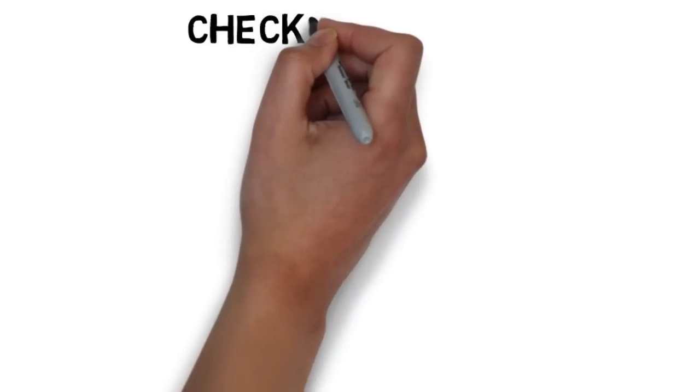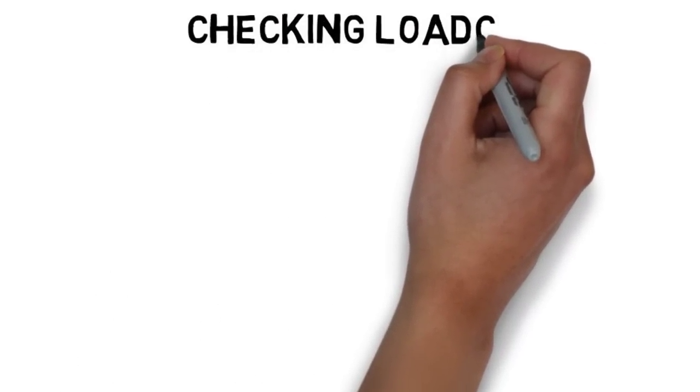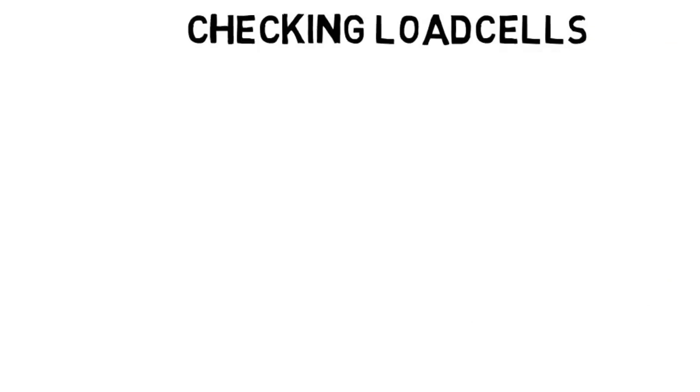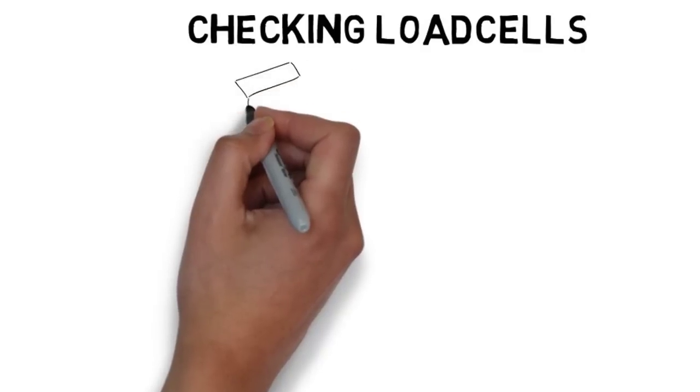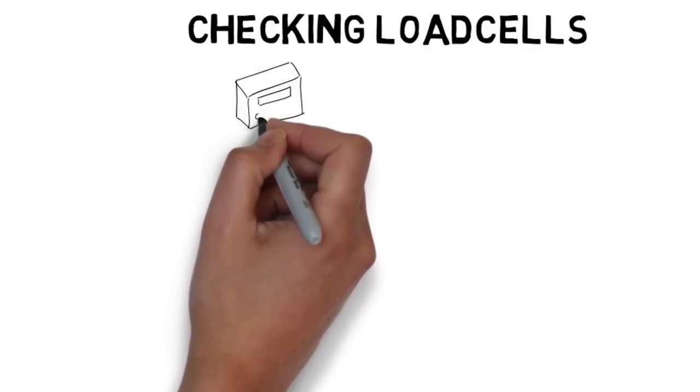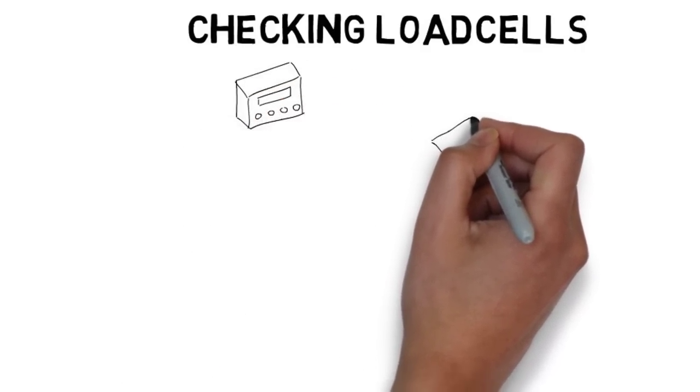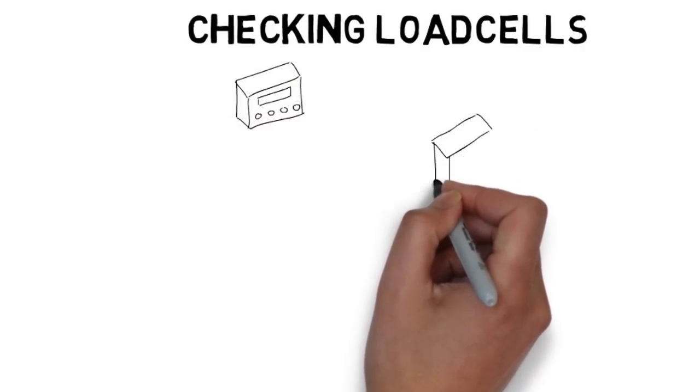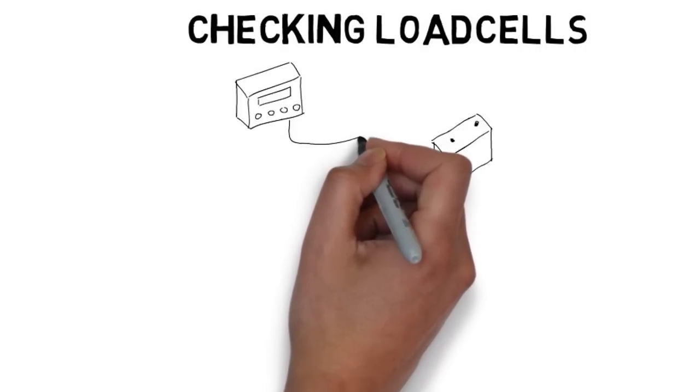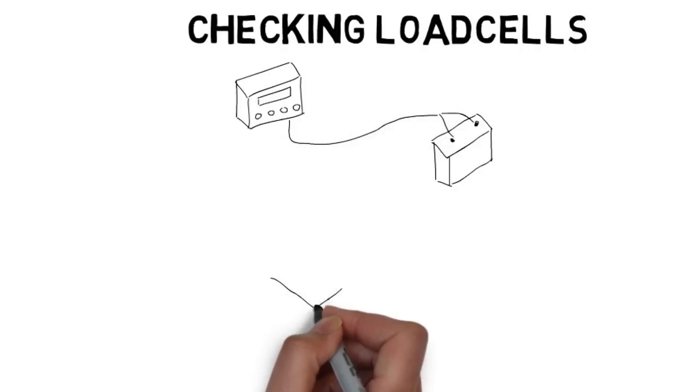Okay, now that we know the power supply and indicator junction box cable and junction box are working properly, we need to troubleshoot the load cells. I'd say 70% of issues with a scale system stem from a bad load cell. The proper way to check a load cell is to check it individually. Try not to use the method of elimination by unhooking each load cell until the problem quits. This can present some issues, especially if you have an intermittent issue on a load cell. It can oftentimes result in replacing the wrong load cell, which can be expensive.